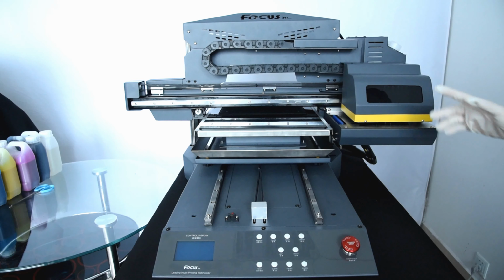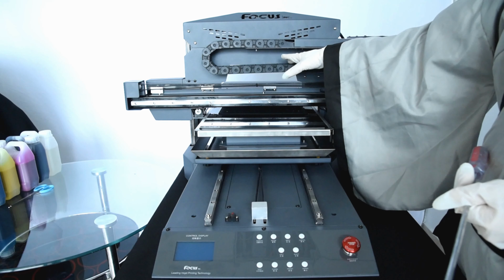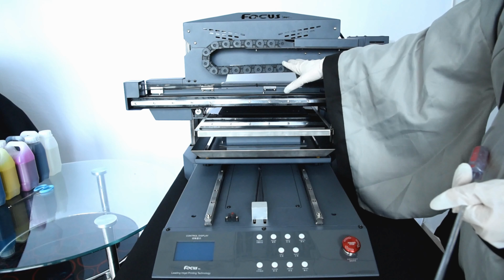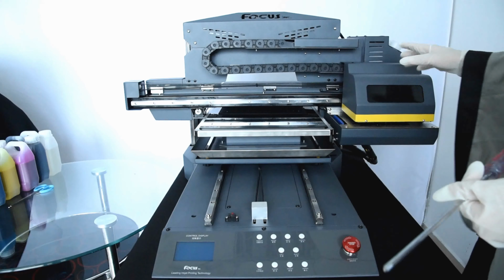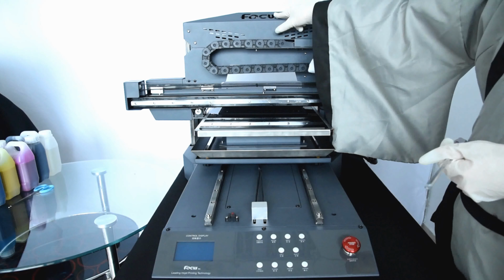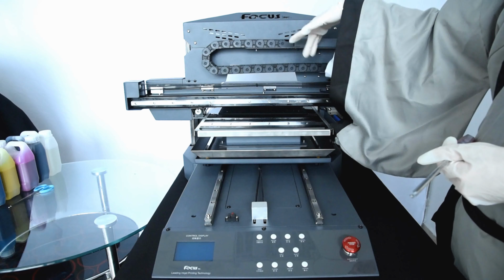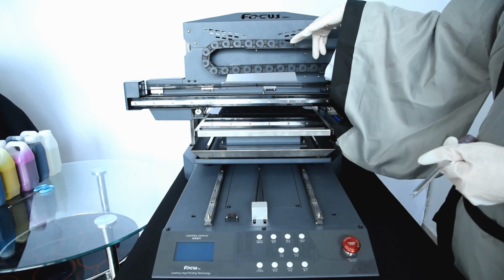This is the tank chamber, inside which there are ink tubes and cables. On top, inside, there's the up-down motor, along with the cable that supplies power to it, and the up limit sensor. When the table moves up and down, this sensor stops it from moving out of position.